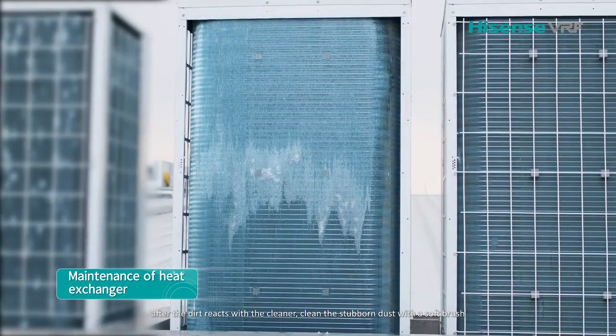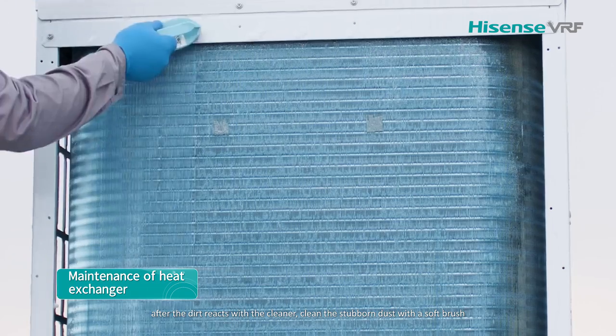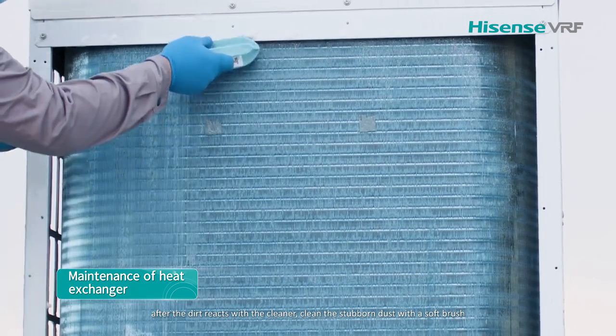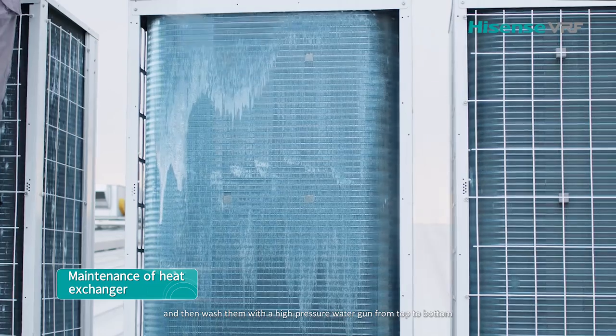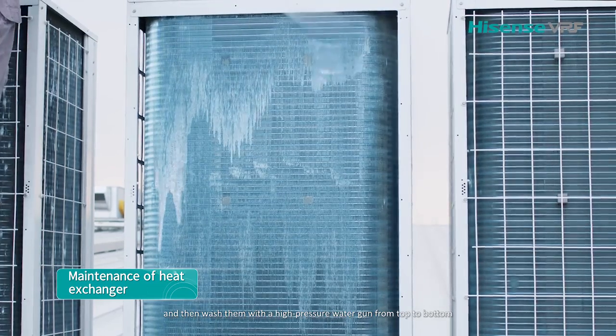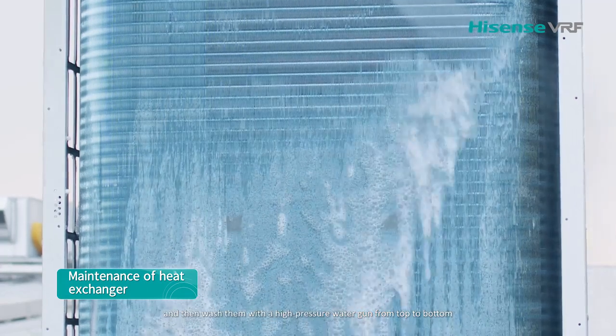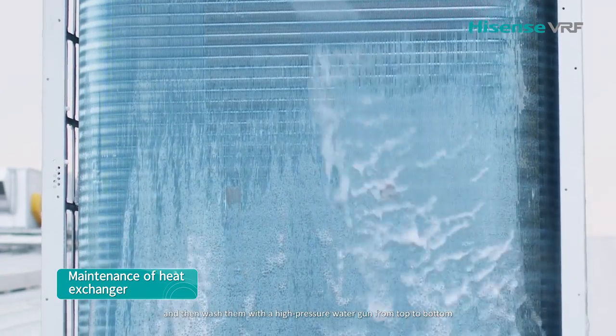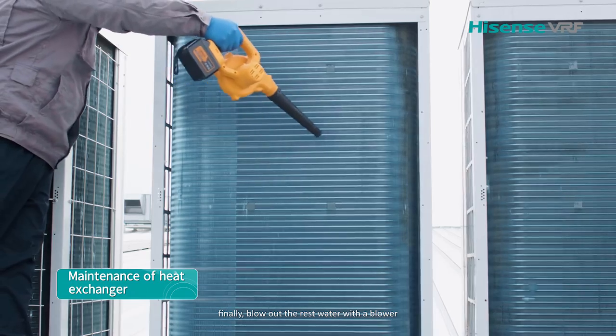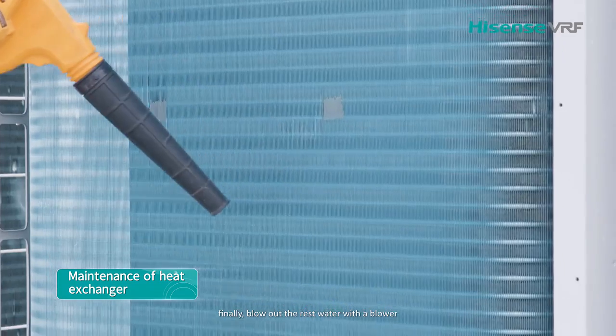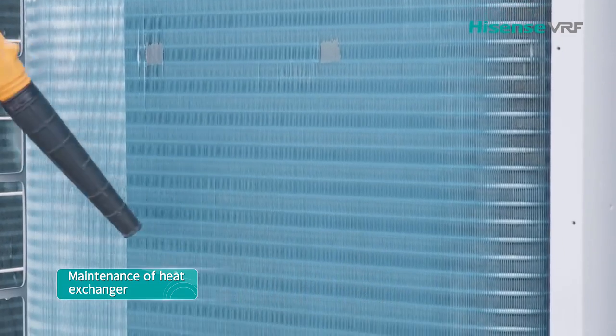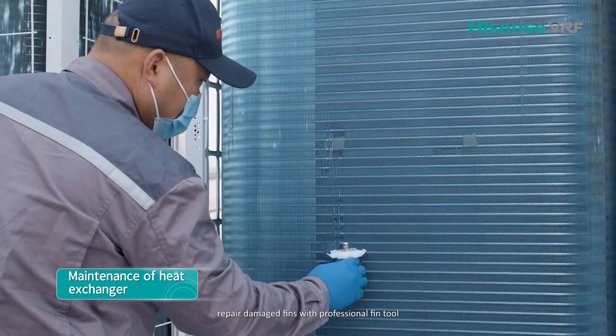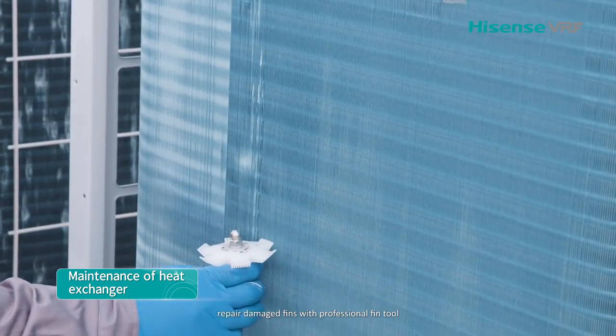After the dirt reacts with the cleaner, clean the stubborn dust with a soft brush, and then wash them with a high-pressure water gun from top to bottom. Finally, blow out the rest water with a blower. Repair damaged fins with professional tool.